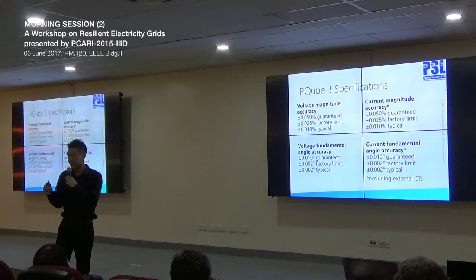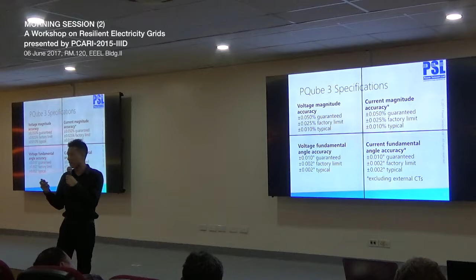And by doing this, by publishing our spec at least twice of our factory pass-fail threshold, we can guarantee that you will not need to calibrate your high-end, accurate, precise instruments until 10 or 20 years. And we got this data after analyzing our drift specifications of all of our internal components.